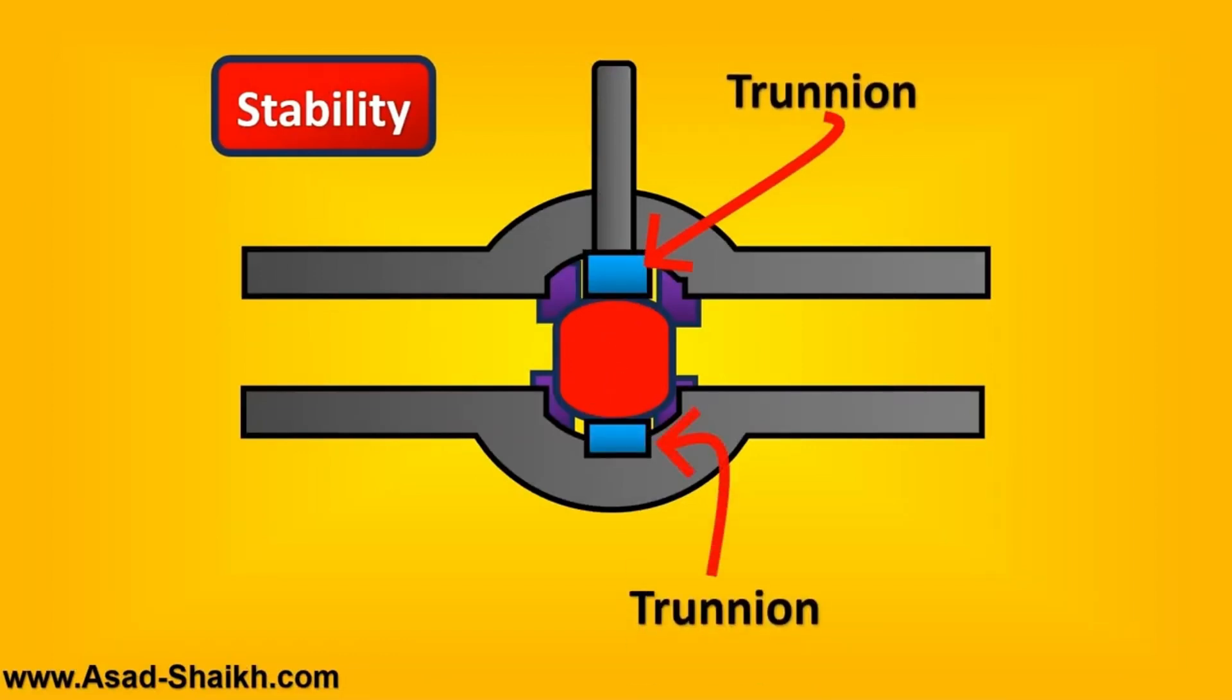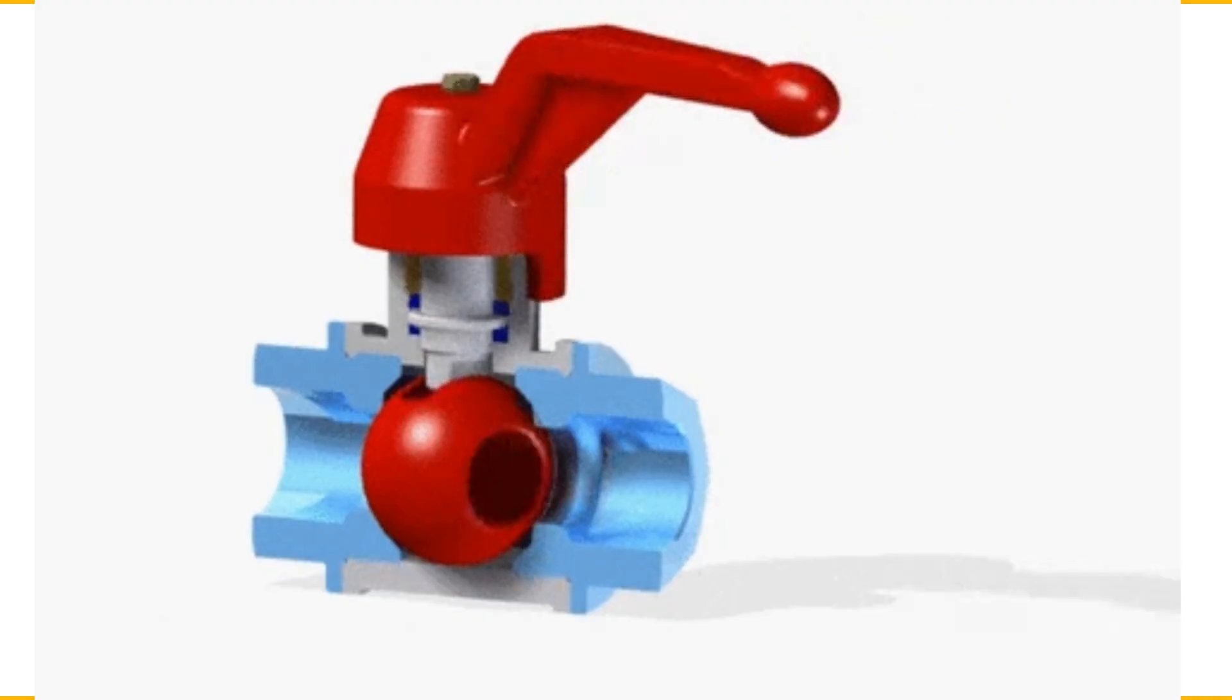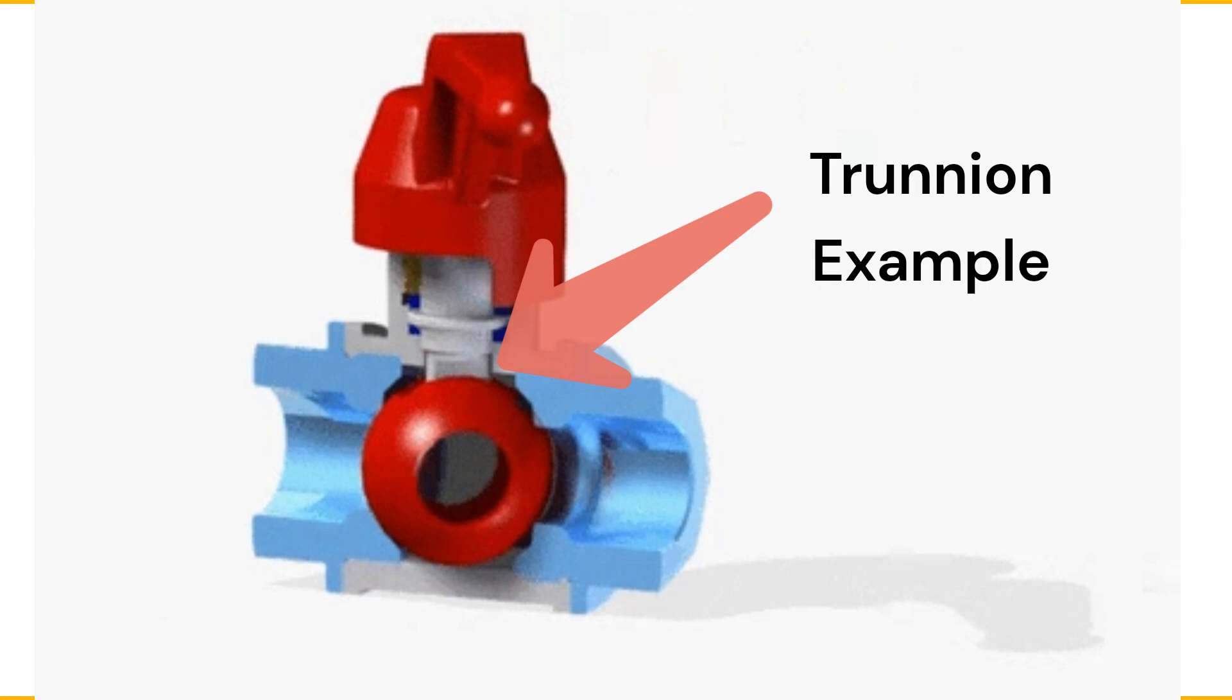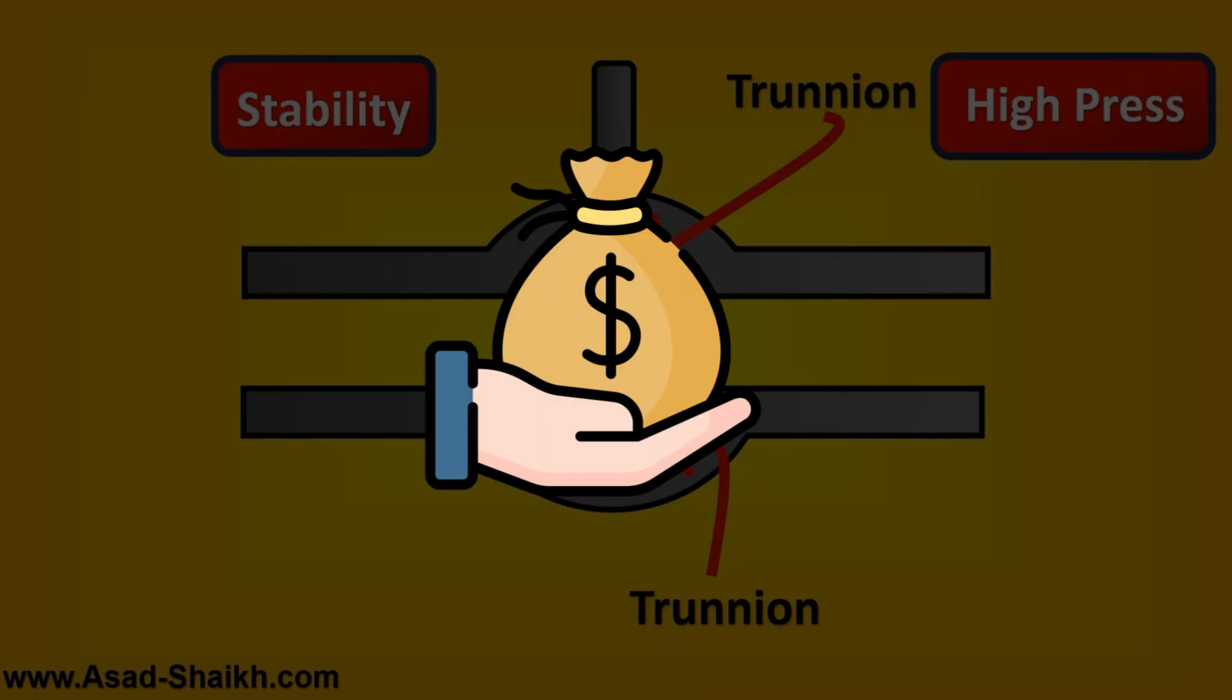This trunnion is basically going to support the valve such that in high pressure drop applications, the ball remains in its place. This is better as compared to floating ball valve when it comes to high pressure applications. However, the cost of a trunnion mounted ball valve is far superior as compared to a floating ball valve application.